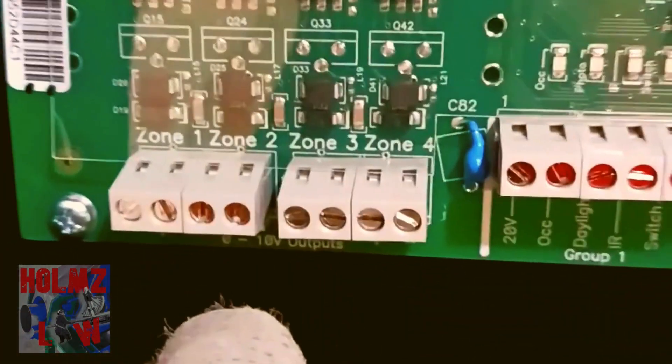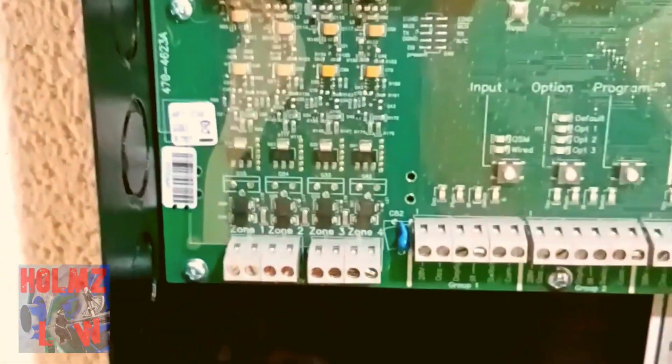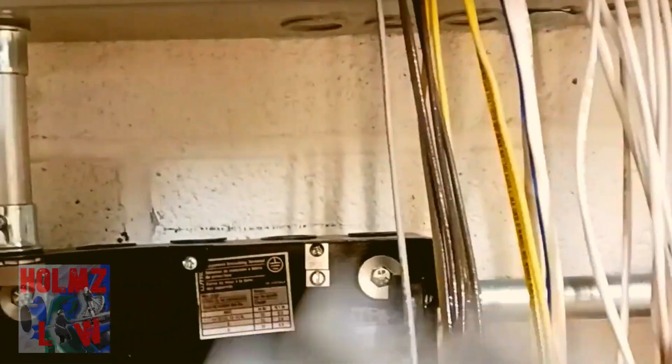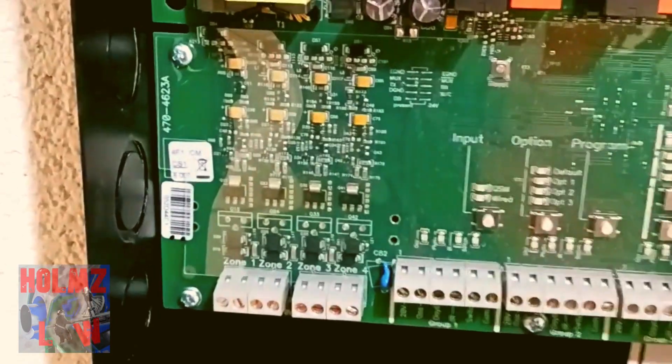As far as the zero-to-ten dimming goes, that gets connected down here. It has a separate zone for each zero-to-ten dimming connection, and if you look further you'll see positive, negative, positive, negative — these are all the outputs where you wire your zero-to-ten dimming. If you're using luminaire cable that's where it would go. We're using conduits so I had to run my power and my low-voltage dimming separately.